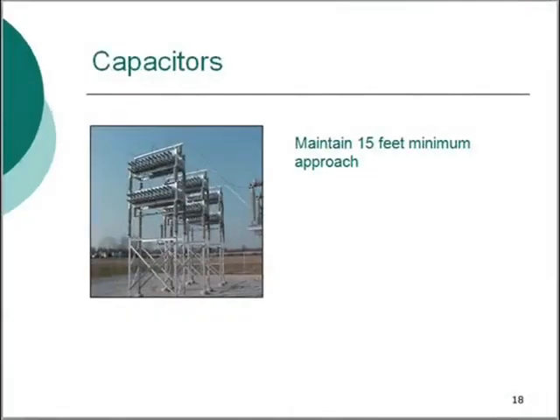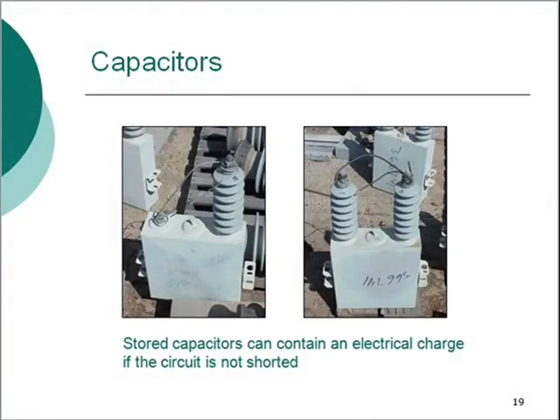Capacitors store electrical charge and increase the efficiency of transporting power across the lines. Capacitor banks are programmed or controlled by dispatch to close automatically without warning. When working near a cap bank, maintain 15 feet minimum approach distance unless you have received additional safety training specific to this equipment. Small capacitor cans are often stored in substations. Be aware that the capacitor can contain an electrical charge if the circuit is not shorted. There should be a jumper attached between the bushing and casing or between the two bushings to create a short circuit. If you find a stored capacitor with a missing jumper, do not touch it. Report the problem to the system dispatcher or your AEP point of contact.